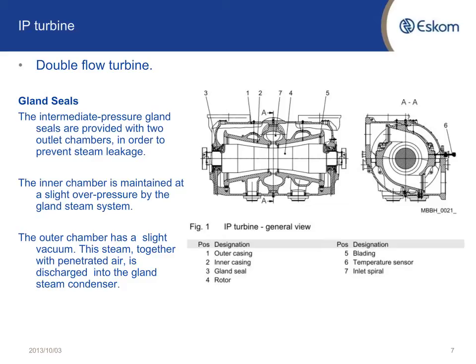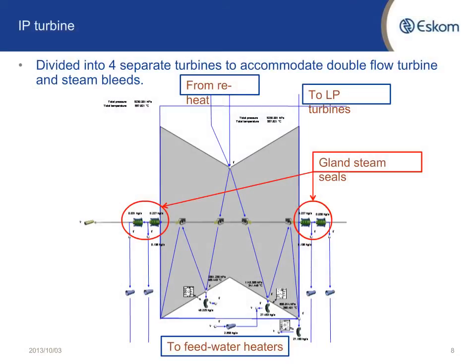That's the reason why I had to split the IP turbine into four separate turbines. In the middle you can see the steam coming in from the reheat, going through the first two turbines, then down through two orifices where the HP steam bleeds are, then going back to the second stage of the turbine, coming out to the next steam bleed, and from there going to the crossovers over to the LP turbines, with two labyrinth seals for the inner and outer chamber of the gland seals.